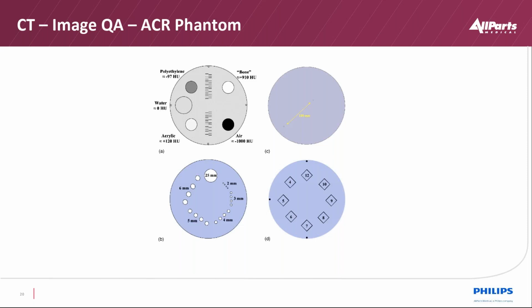And then one of the other things that's very hard to tell on a CT scanner is resolution. We want to make sure our resolution matches really well. So not only do we have line pair resolution, like on the scaling that we see here, represented by the numbers, there'd be different line pairs, but also on what we call B, where you have different size elements there. The difference between the material is only 6 CT numbers difference in that phantom. So if I don't resolve that 6 CT number difference, I can't see small changes in CT numbers. So one of the things could be maybe the technique wasn't high enough to basically enhance the data set, or the wrong filter was used, some of those things. So we always are validating the quality of the images we generate on a CT scanner. So it's pretty exacting. Over the time, the scanners have been much more reliable.